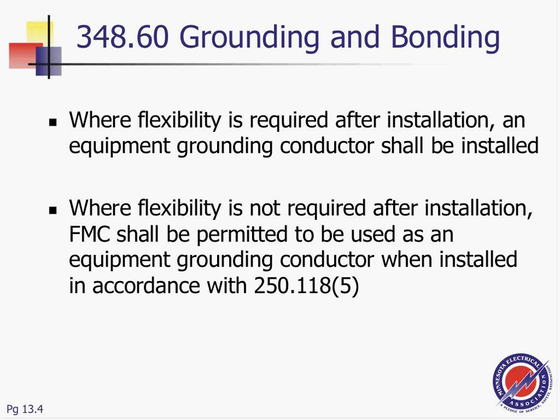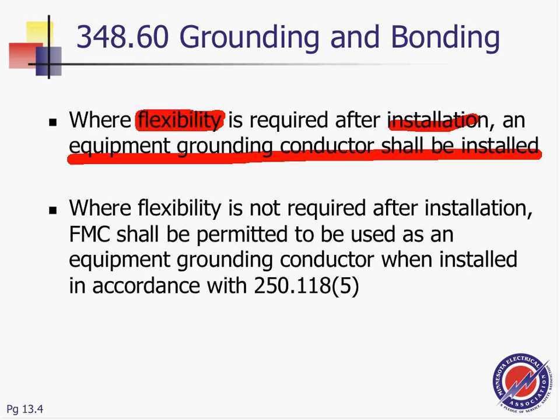Okay. Grounding. The truth when it comes to grounding. If you are tying because of flexibility, which is what we always thought for equipment, after you install the flexibility and equipment, you have to put an equipment grounding conductor, which, Kevin, my friend, 99% of the time when you tie to equipment, you tie it because of what? Flexibility and vibration coming out of it. So what do you need to do if you're tying to equipment? You need to pull an equipment grounding conductor.